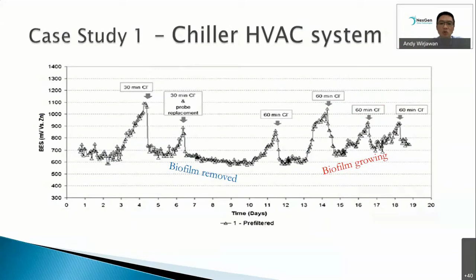But in terms of biofilm formation, it is probably not good to have it at 100,000 or less than 100,000. It has to be a lot less. So as you can see, despite the continuous dosing, the biofilm is still growing on the equipment. And toward the 13th, 14th, 15th day, there are certain changes in the cooling tower water. As you can see, even the continuous dosing is unable to maintain it, and the biofilm continues to grow. Okay, next one.